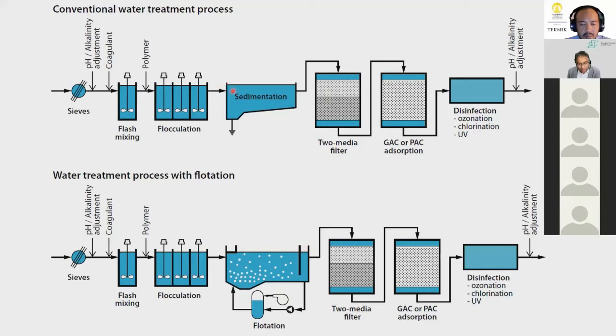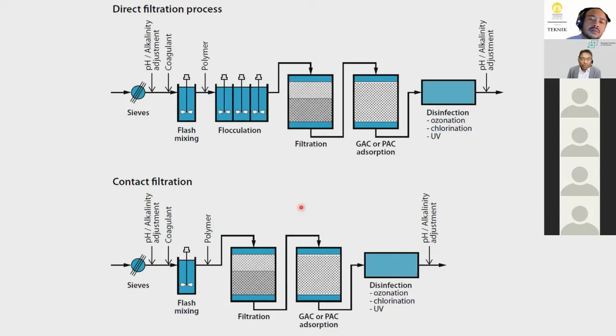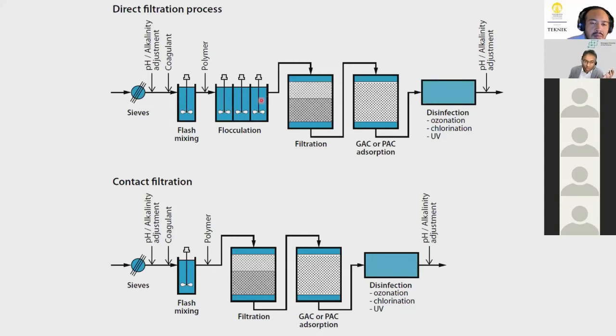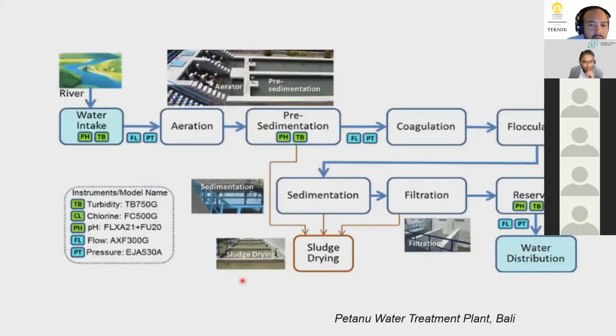More advanced systems add filtration after the common treatment sequence. Flotation can replace or supplement sedimentation, where dispersed pressurized air is added and sludge is skimmed from the top. Two more efficient systems are direct filtration — which includes flocculation but skips sedimentation, sending flocs directly to filtration — and contact filtration, where there is no separate flocculation stage and floc formation happens inside the filter. Contact filtration suits water with low turbidity and suspended solids.